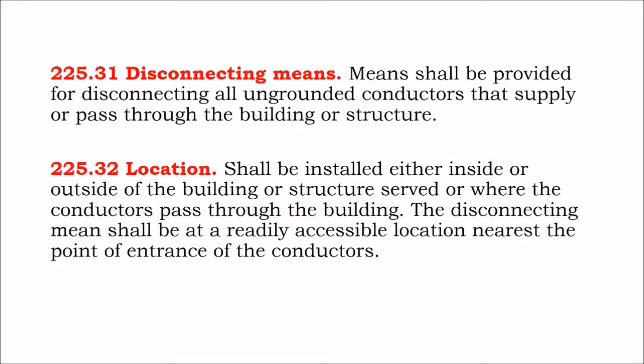For instance, if you want to have an autonomous, automatic relay between your utility and your transfer switch and your on-site generator and your solar array and your battery bank, where when the power goes out, you want the switch to flip and you want to go on to your battery bank, and then you want the generator to turn on when your batteries deplete, but then when the power comes back on, you want to switch back on to grid power, and you want it all to happen automatically. Well, you may need to have a neutral be fully connected throughout the entire system in order for that kind of automation to occur, so that you can monitor the status of the grid versus the status of your generator versus the status of your battery bank.